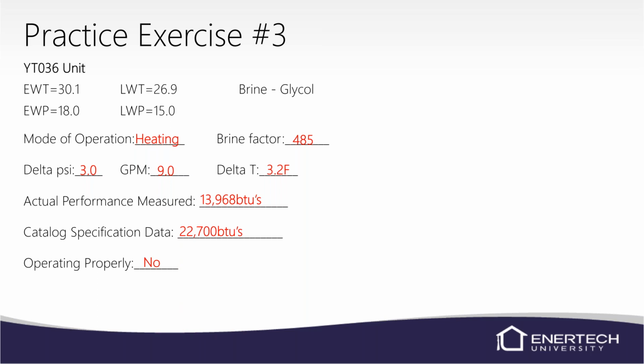So before you throw your refrigerant gauges on there, what I would look at is this is a 2-stage unit. We're running about 2/3 capacity. So maybe the unit's not shifting into the second stage, because when we run in first stage, we run 2/3 capacity. The other third comes in when we switch to second stage. So this might be that the solenoid on the second stage is not working, or the thermostat's not giving us a Y2 signal. So that's the first thing I would check.